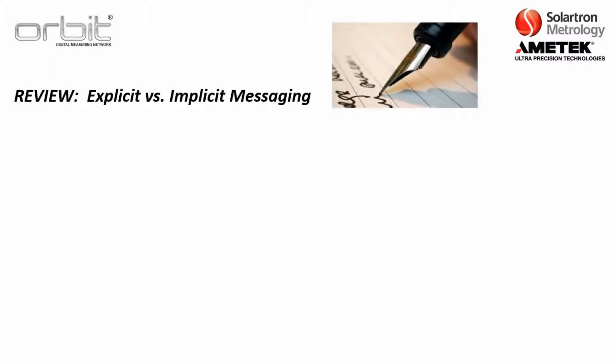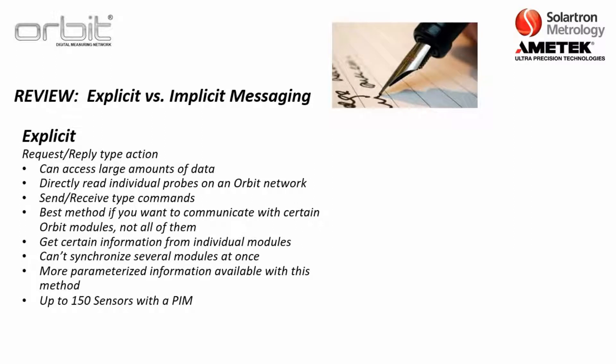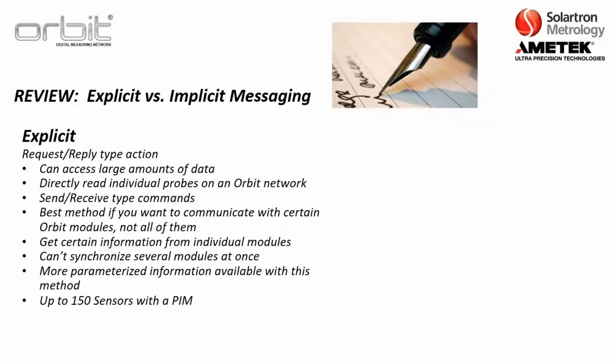Now just a quick review, one of the things that's discussed frequently about connecting to the PLC is explicit versus implicit messaging. Now explicit messaging is basically a request reply type action from the PLC and with this you can access a large amount of data. And so with this you can actually directly read individual probes on an Orbit network. So let's say you just want a reading from like the fifth probe loaded onto the Orbit stack, you can do a send or receive type command for that. So this is the best method if you want to communicate with certain Orbit modules, but not all of them. But it should be noted that with this mode you can't really synchronize several modules at once, but you have more parameterized information available. So with this particular mode you can do up to 150 sensors with a PIM.